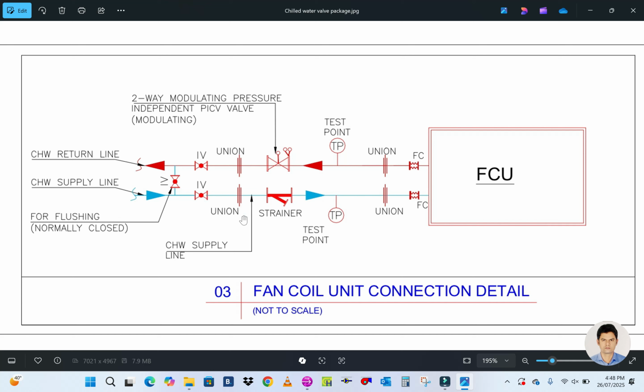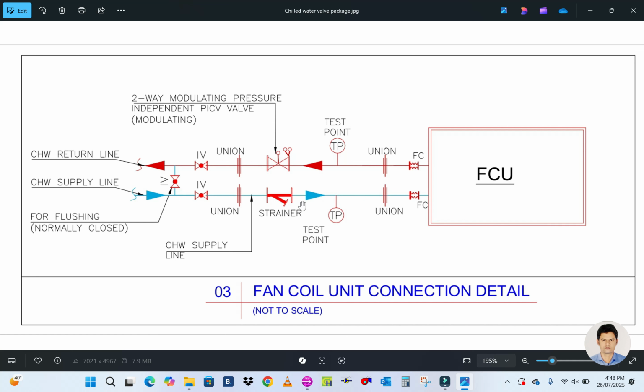Next, the second fitting is a strainer. A strainer is always fixed in the chilled water suction line. Chilled water suction line means the supply line, because the water is coming from the chiller and going to the FCU. So if there are any foreign items, they can be strained out through the strainer. Next will be the flexible connection.